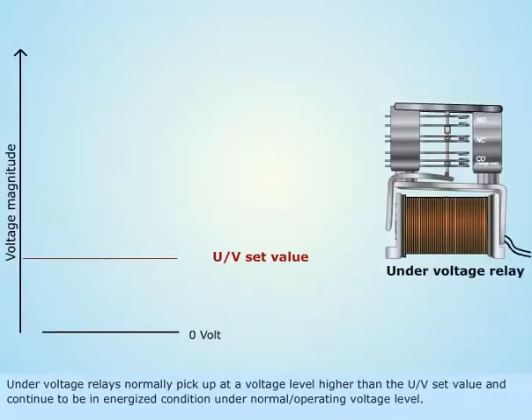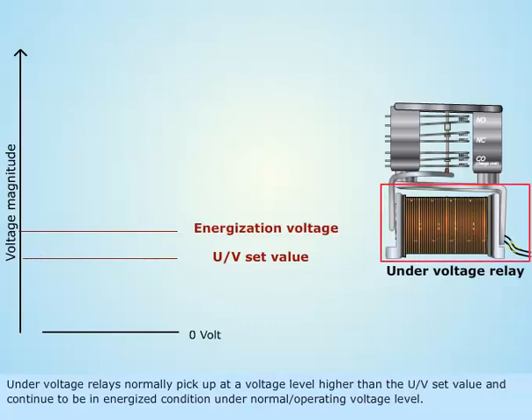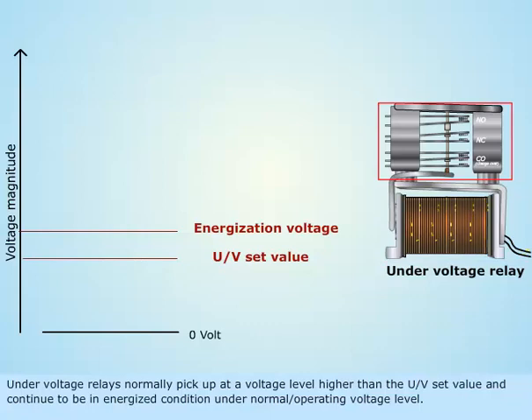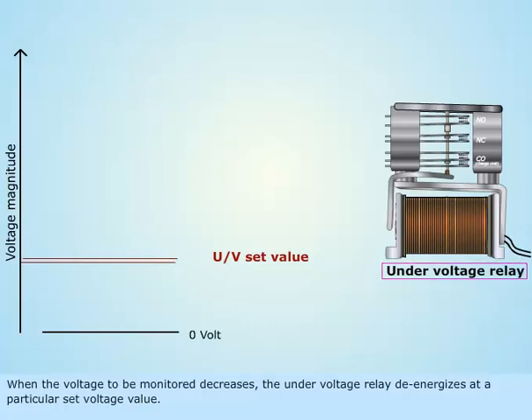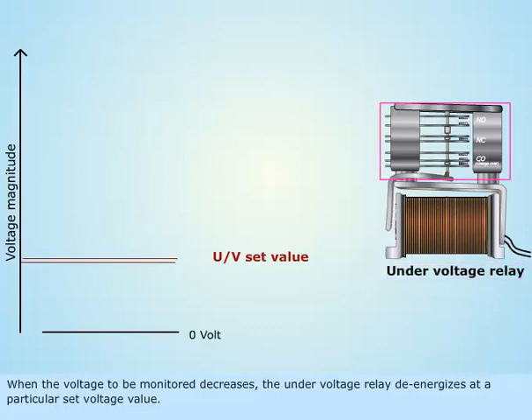Under voltage relays normally pick up at a voltage level higher than the under voltage set value and continue to be in an energized condition under normal or operating voltage level. When the voltage to be monitored decreases, the under voltage relay de-energizes at a particular set voltage value.